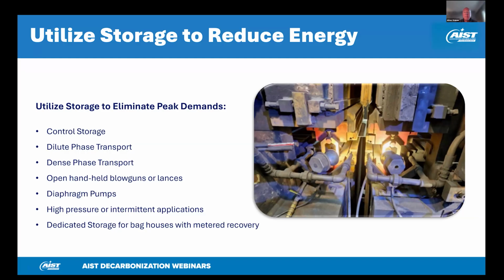Storage provides time. So if we can store air in the compressor room at a few PSI higher than we actually need in the header, and we can separate the supply system from the demand system with the pressure flow control valve, we can utilize that control storage to meter out to the plant and keep the pressure steady, versus keeping a compressor in hot standby, blowing off. We can use storage to handle those peak demands. Some of the peak demands that you see are any kind of dense phase or dilute phase transportation. We can use dedicated storage there with metered recovery, and I'll show you an application using that.